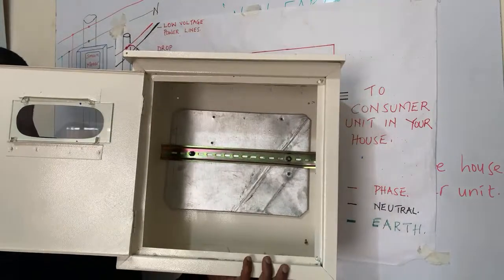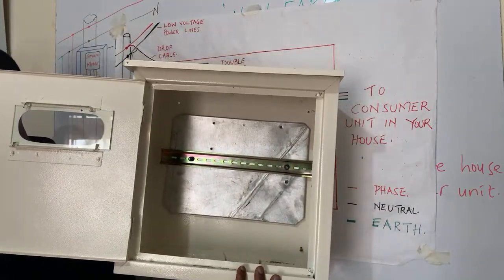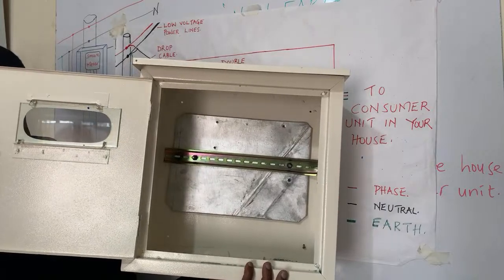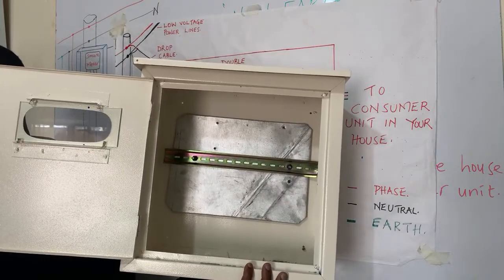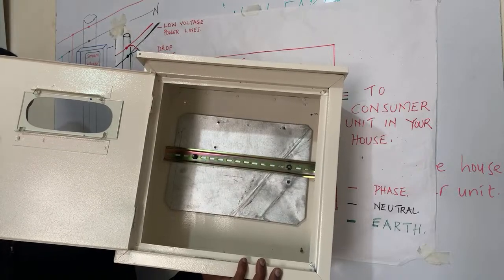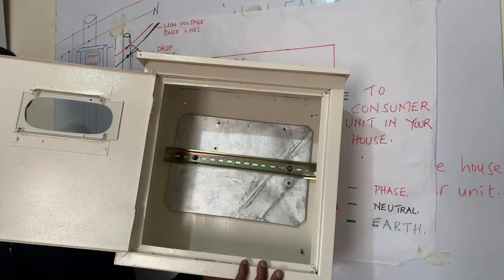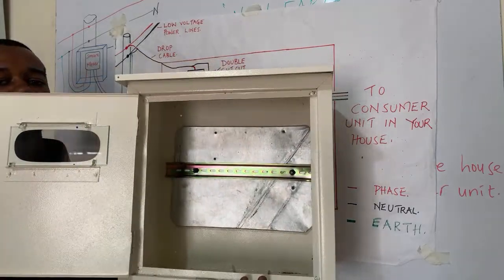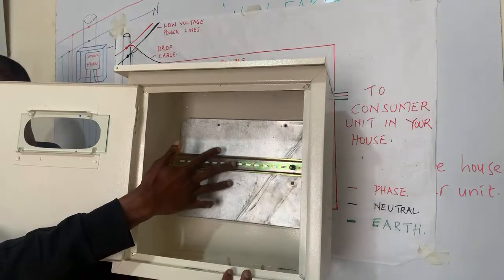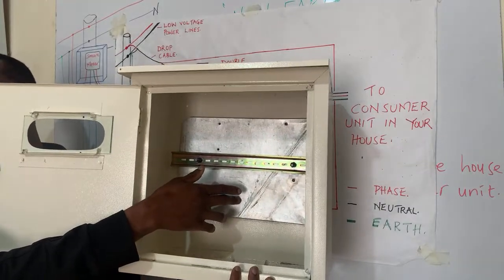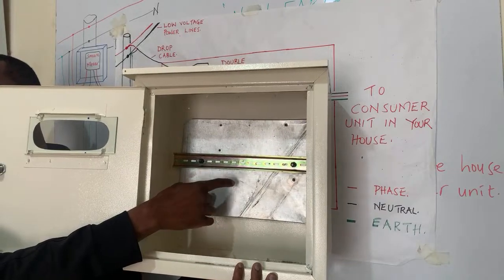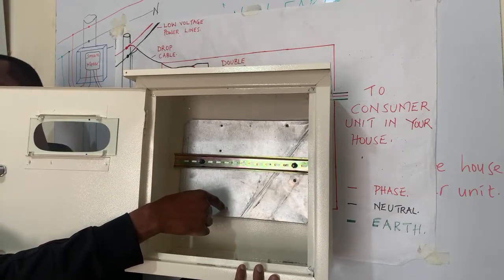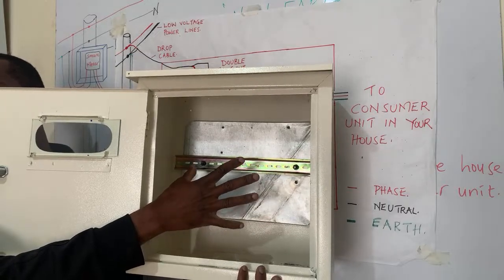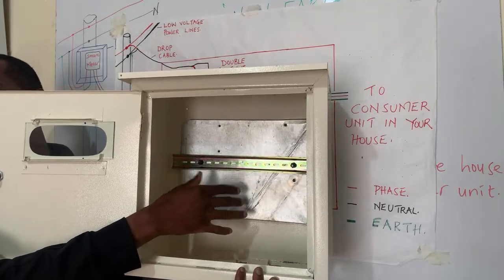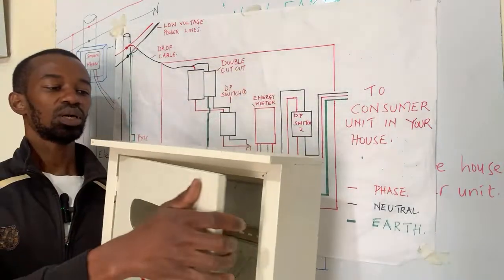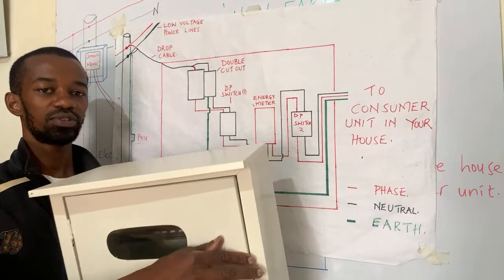There are other meter boxes whereby you'll find that at that particular point where you need to have a connection, the connection for the cutout, the connection for the double pole miniature circuit breaker, as well as the energy meter, you find that some meters, especially back in the days, this metallic part was not there. There was a wooden part so that it could allow for the screw and also for the mounting of every other feature that will be in the meter box. But nowadays, that one is not there because of safety reasons.